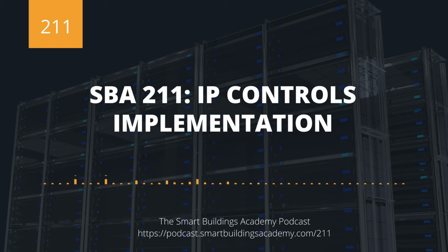Usually what I like to do is a star pattern to an air handler and then MSTP to all the field controllers downstream. I really don't see the point of IP controls for terminal units. I just don't see the benefits at the cost point. Really, do you need graphics on your terminal units? Do you need the ability to run schedules and alarms and trends right at your terminal units? I mean, do you really need that?